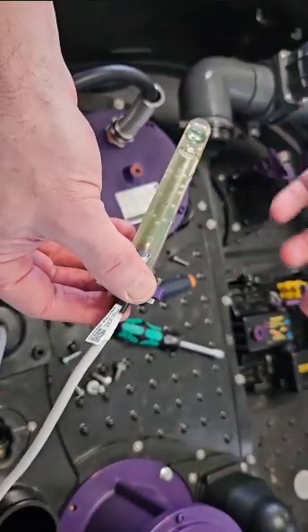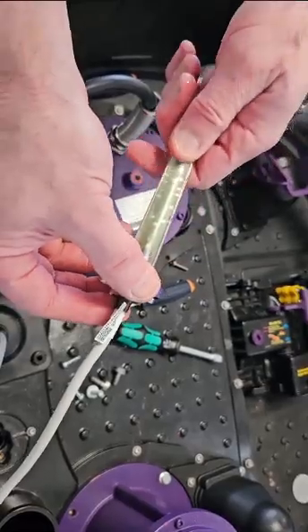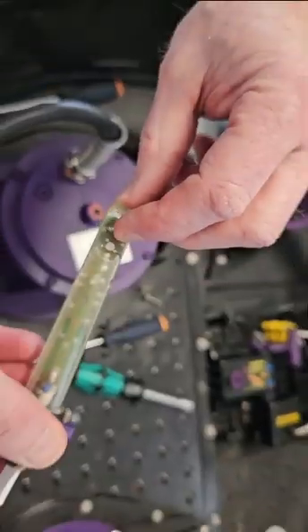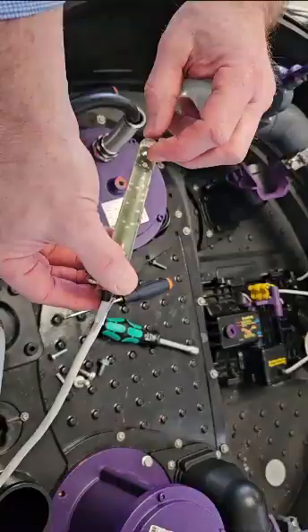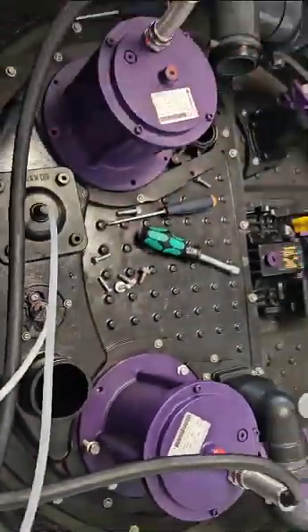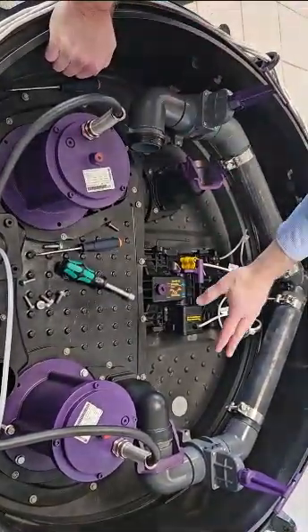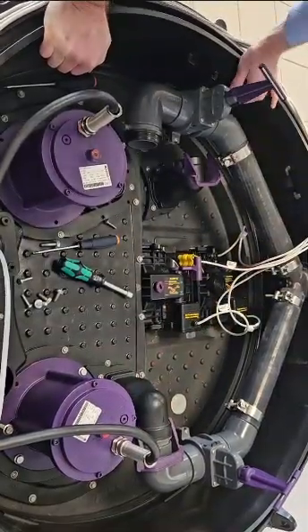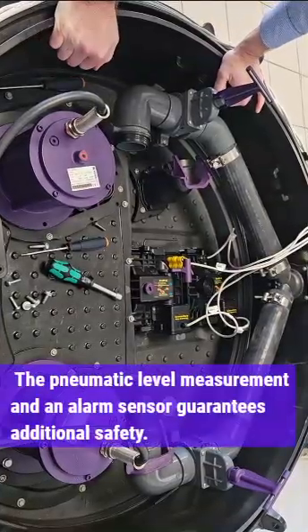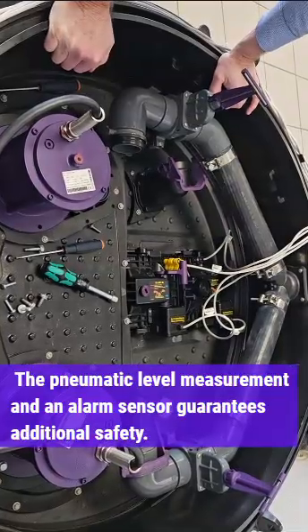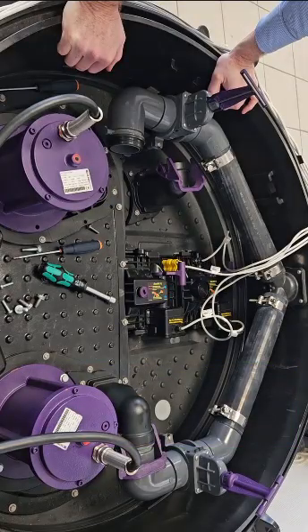Just gonna drop this back in here. We're going to then also remove with the 4 Torx screws the air pressure switch. There's no electronic or mechanical components in here at all. We just want to make sure this is free of any type of debris, which is normally the case. If not, it needs to be cleaned. And finally is our alarm backup probe. This is the 3rd probe that monitors alarm. So if for some reason the pumps are not working or you have water levels exceeding the capability of both pumps, the water level will reach the 3rd optical probe. Then you'll have an alarm letting the user know that the system is completely full of water. Both pumps are running, but for some reason we're not being able to drain out the water. And again, here we have a clean probe with a white litmus piece of paper, meaning the probe is dry and in perfectly good operational condition.